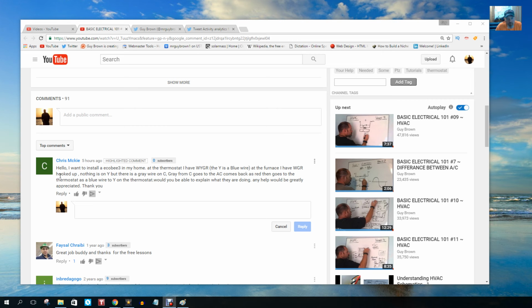And at the thermostat, he has, like you would expect, a WYGR. And on the furnace, he also has the same terminals, but the thermostat wires that he has connected at the thermostat, which is a WYGR, and Y being blue in this case, goes down to the furnace, and the only thing connected is WGR, or white, green, and red. The blue wire goes straight to and connects to another wire, and runs out to the AC and back, and now I'm going to explain why it's wired up that way.